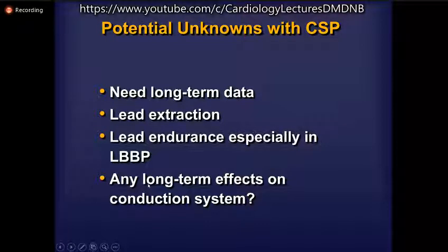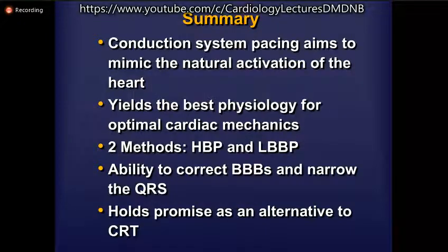There have also been concerns raised about the endurance of the lead, especially with regard to left bundle pacing, where you are burying almost 1 to 1.5 centimeters of the lead within the thick interventricular septum. With repetitive cardiac motion, whether there is going to be any structural damage to the lead or the insulation in the long term is a concern. But so far, there have been no indications of any such deleterious effects, and also whether there are going to be any long-term effects of the presence of the lead on the native conduction system. So hopefully in the future, we'll continue to get answers to this.